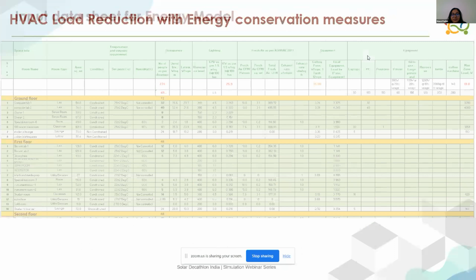So once we have the energy model ready with certain envelope properties and internal gains, we check the peak cooling loads, and we ensure that that is in the range of 200 to 400 square feet per TR. And then we start looking into various measures, which are, say, envelope measures and lighting measures. And then we start checking the percentage reduction which each of these measures provide in terms of system sizing.